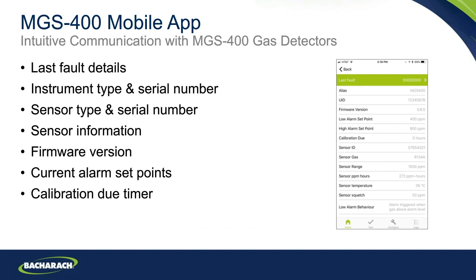Lots of information is available to extract from the app, including information on any faults that have occurred, the instrument details of type and serial number, and the sensor types, of course, are detailed separately as well because they are that interchangeable module. Also got firmware versions within there, and you can view current alarm set points that are configured. And one thing that's pretty important here as well is we have a calibration due timer. So there will be a countdown here that will provide an alert to you to advise of when maintenance should be undertaken on the system.